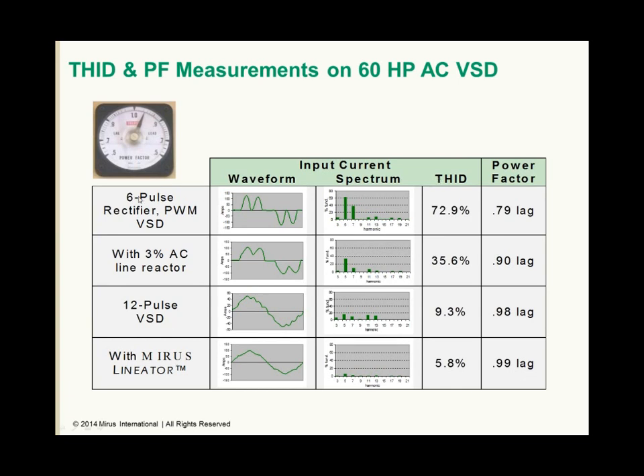Here we can see, for a 6-pulse diode bridge rectifier pulse width modulated variable speed drive, the typical double humps of pulsed current. So this is not a sinusoidal current. Being non-sinusoidal, it contains harmonics. It has a 5th harmonic component, 7th, 11th and 13th, predominantly the odd order harmonics. The total harmonic current distortion of this waveform is 73%. The power factor is 0.79 lagging.